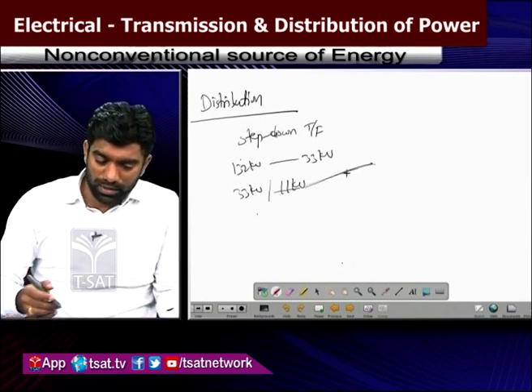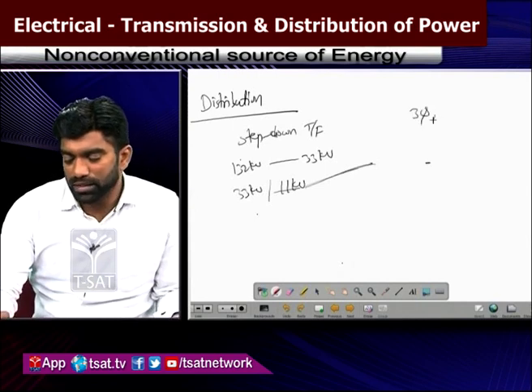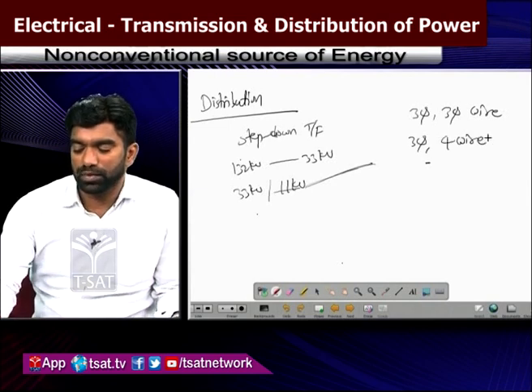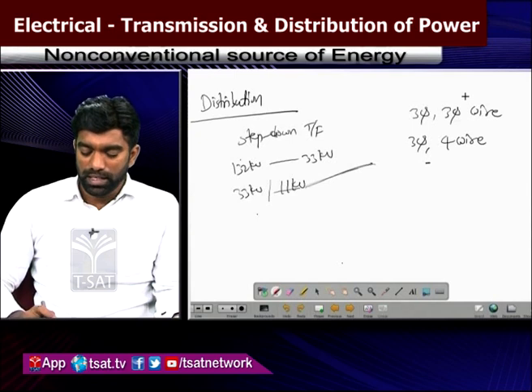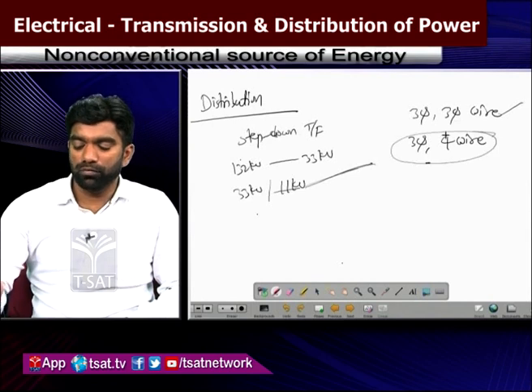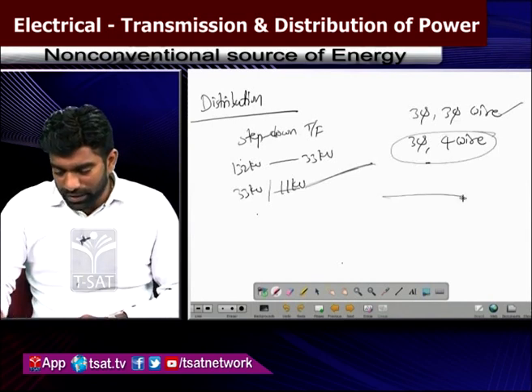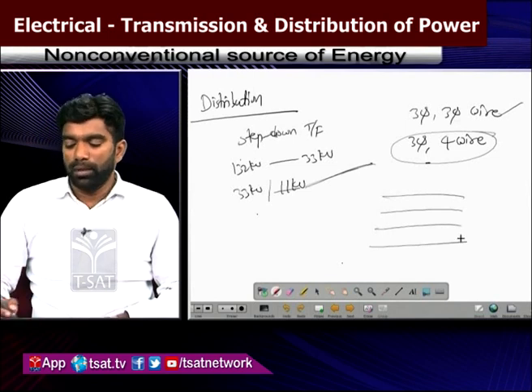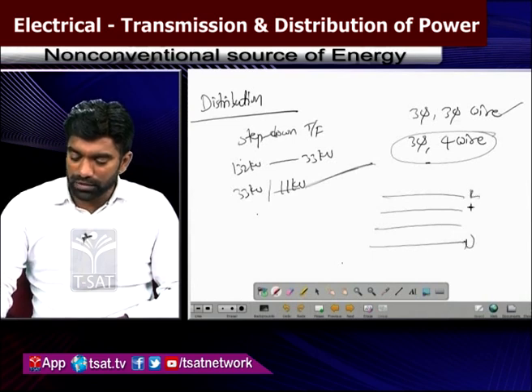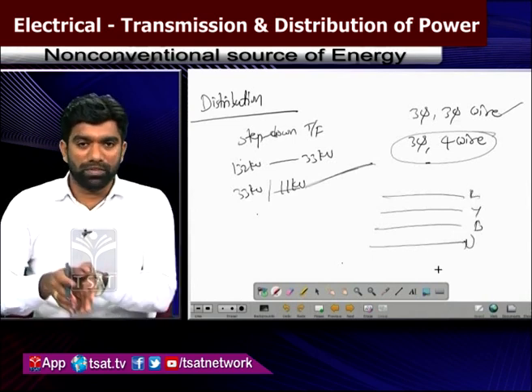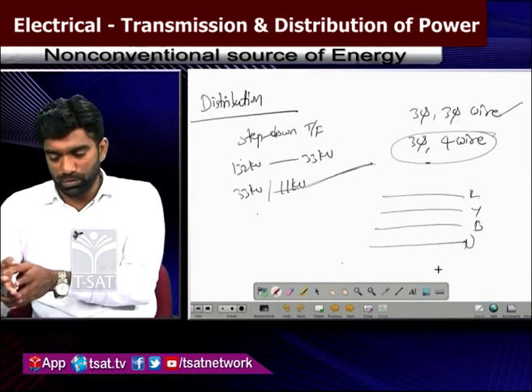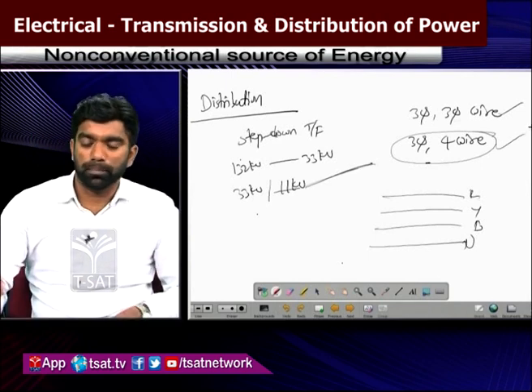Distribution is also of two types: three-phase three-wire system and three-phase four-wire system. In the three-phase four-wire system, the fourth wire is the neutral wire. The advantage of taking the neutral wire is that by using R phase, Y phase, B phase, and neutral, we can take three separate single phases. For distribution, a compulsory four-wire system is taken.